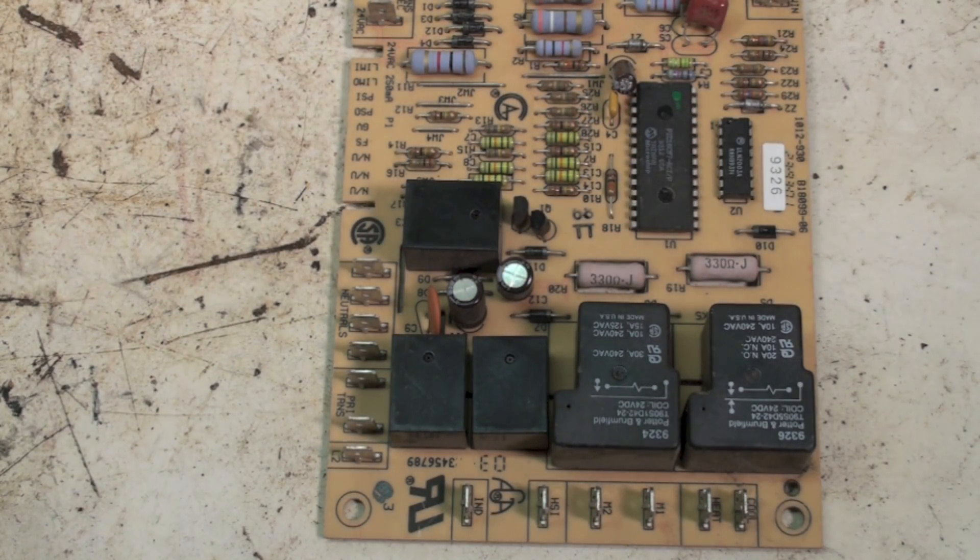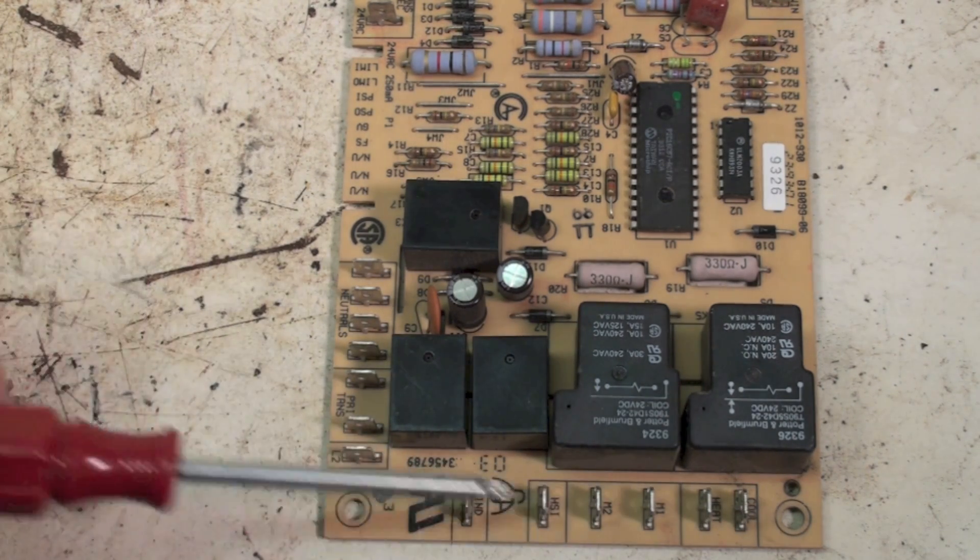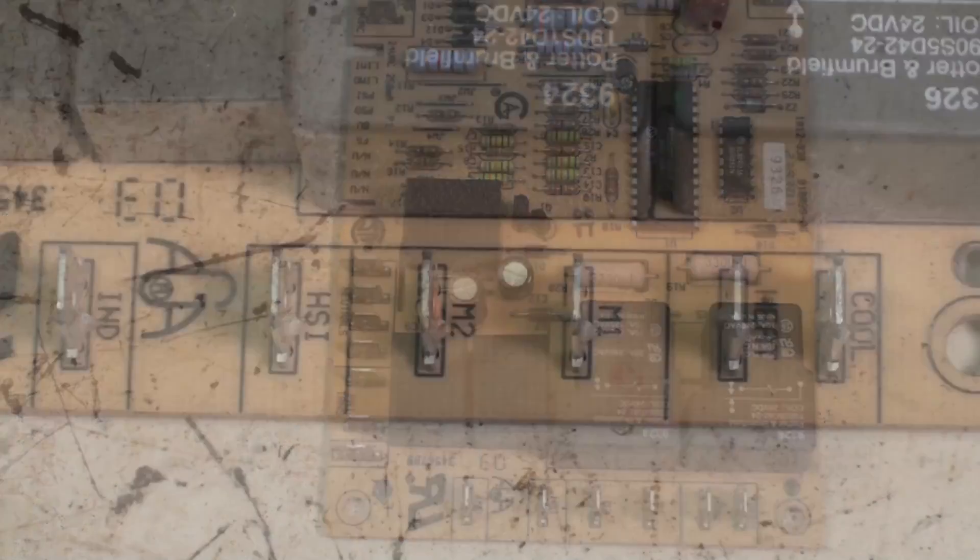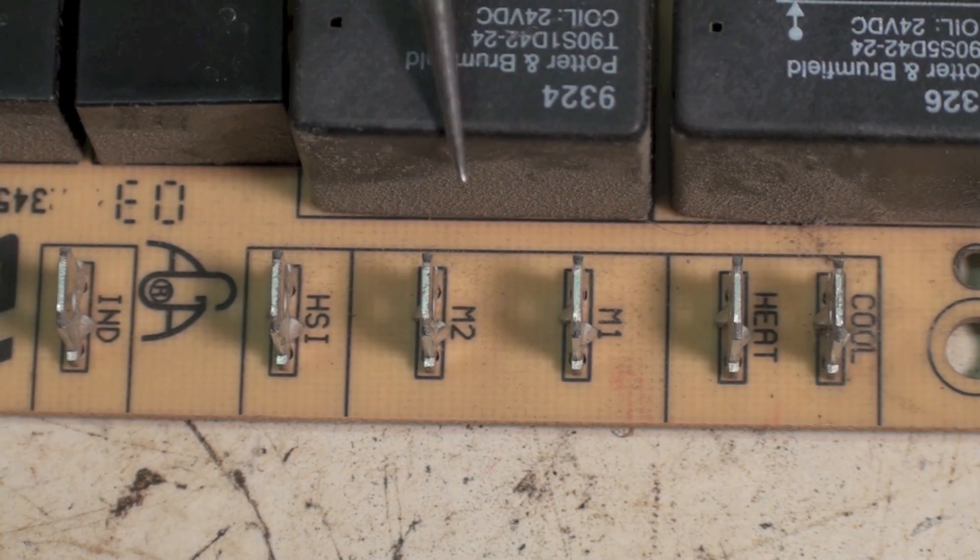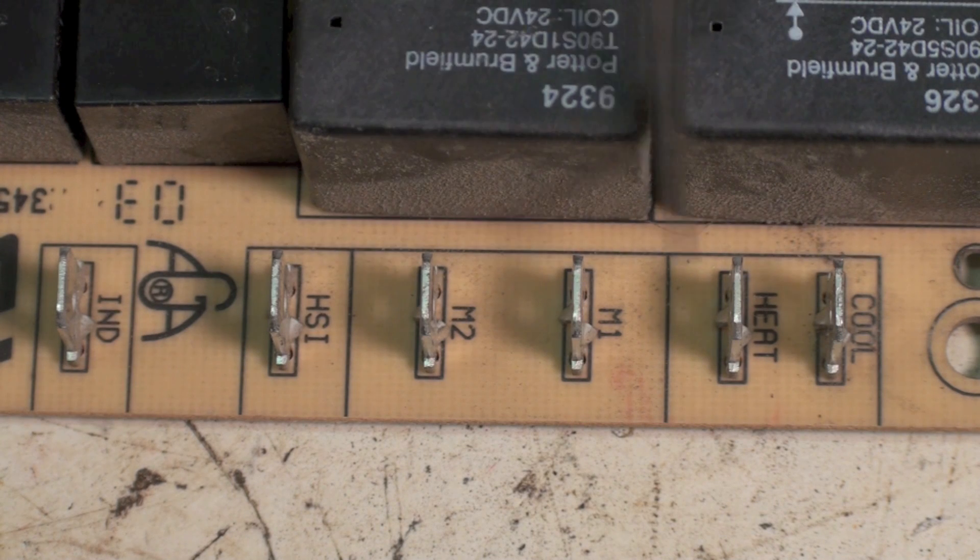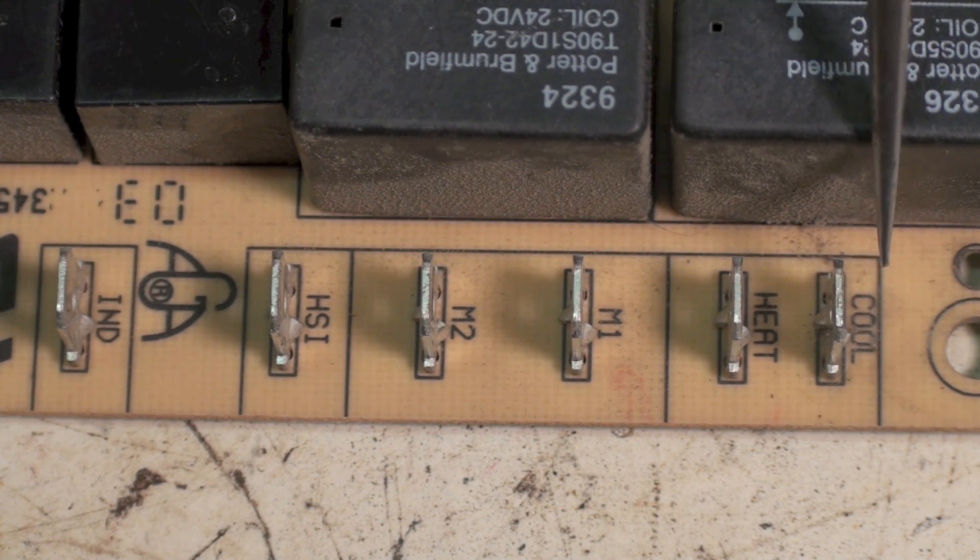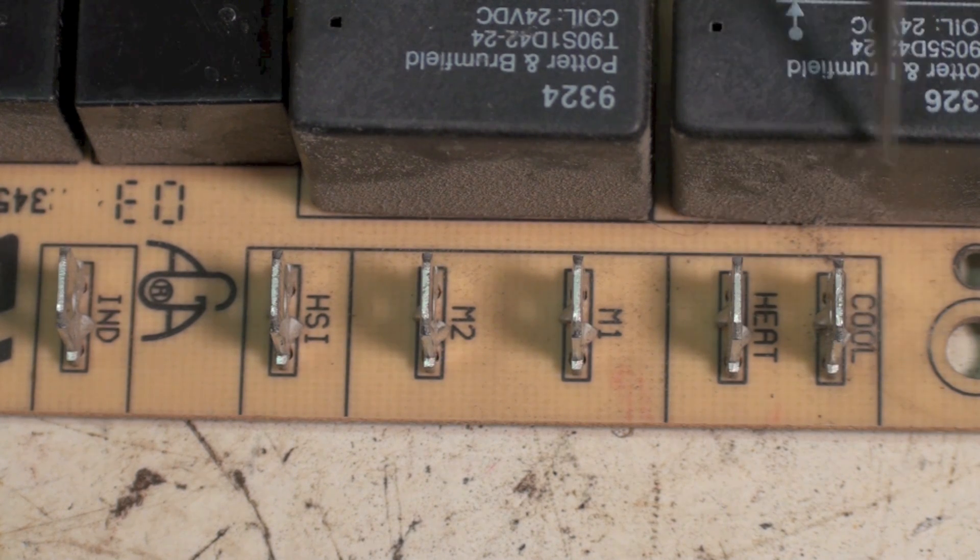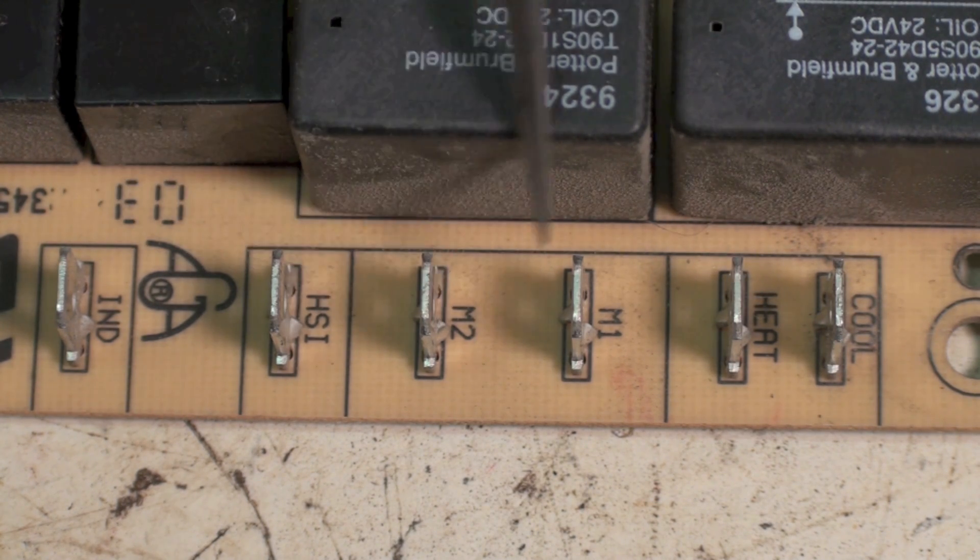The motor wires will probably be mounted along in here. This one says 'cool' on it, so that's a cooling speed. Cool is usually a higher speed than heat - not always but oftentimes. This is for heat. Now these two terminals called M1 and M2, they're not hooked to anything.